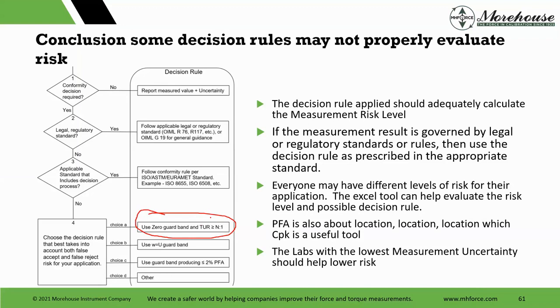So the decision rule, a little bit of wrap up, and then we'll take questions. The decision rule applied should adequately calculate the measurement risk level. If the measurement result is governed by legal or regulatory standards or rules, then use the decision rule as prescribed in the appropriate standard. Everyone may have different levels of risk for their application. The Excel tool can help evaluate the risk level and possible decision rule. PFA is also about location, location, location, which Cpk is a useful tool, and that's the probability of false accept. And the labs with the lowest measurement uncertainty should help lower risk.